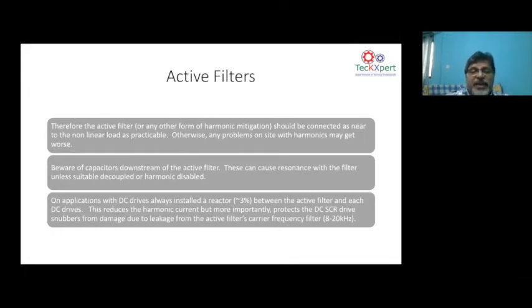And also, when you're putting a capacitor bank, make sure the capacitor banks are detuned. If your capacitor banks are not detuned, then there is a question of resonance, because active harmonic filters also produce harmonics, and there can be a possibility of resonance with the capacitors in the network. Without detuned reactors, you should not put capacitors.